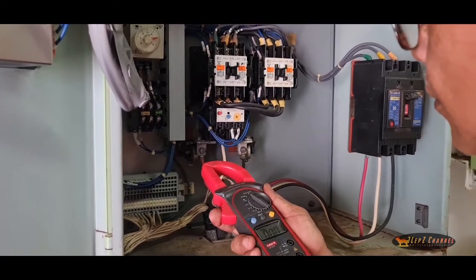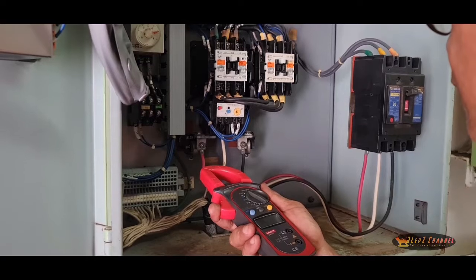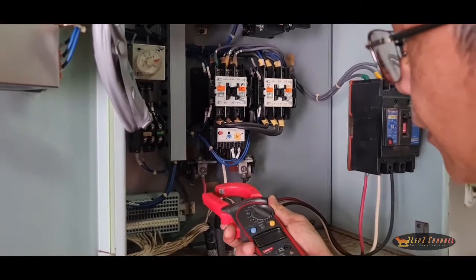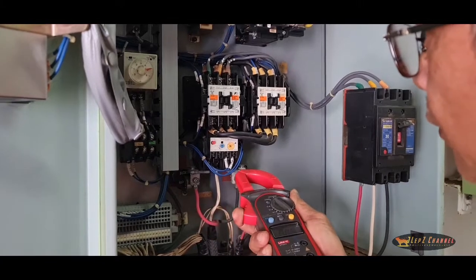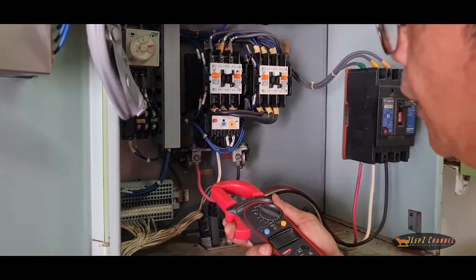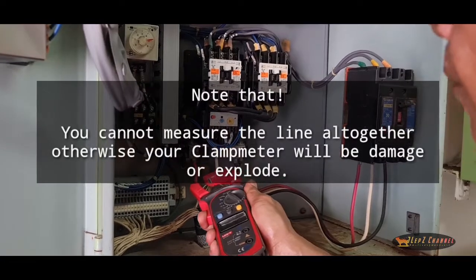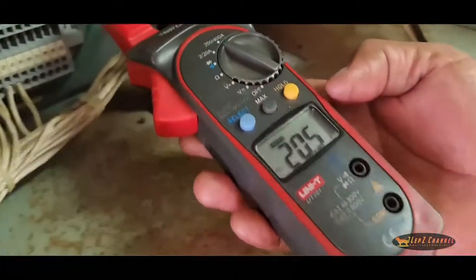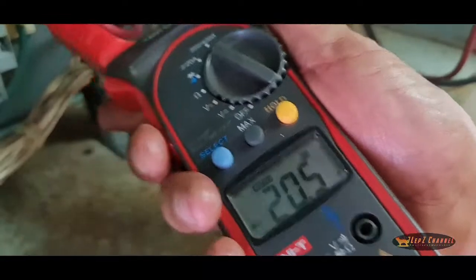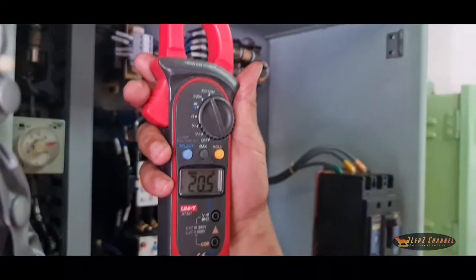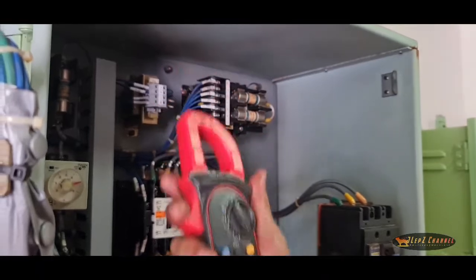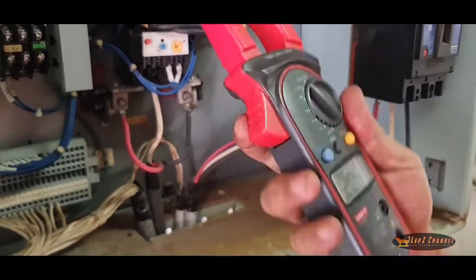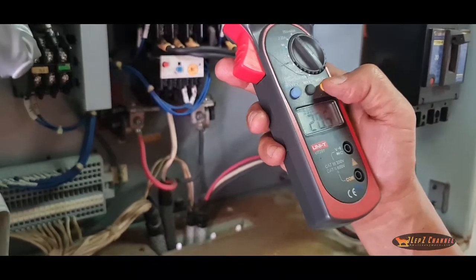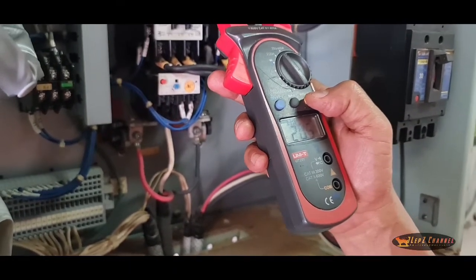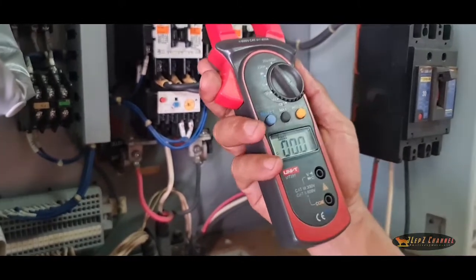Now, by inserting this clamp to line 1 and to line 2 or line 3, you will know what the line current is. For example, like this, line 1. Now the reading is 20.5. You see, this is 20.5 for line 1. Now I will press to release the current, 20.5, release the hold. Now it goes back to 0.